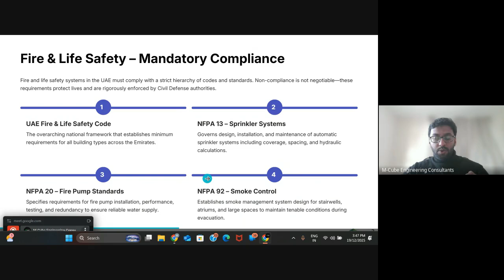So try to be aware of the upgrades in the codes which are happening related to your local emirates, and try to follow them to avoid rejections. And again, the UAE fire code is formed from the parent codes which come from NFPA. So we have NFPA 13 for sprinkler system, NFPA 20 for pump standards, 92 for smoke control, and many other NFPA standards which are all integrated into one code for us, which is the UAE Fire and Life Safety Code.